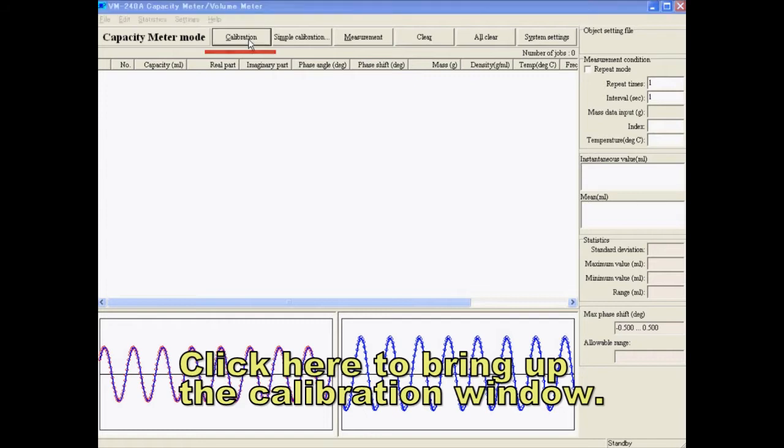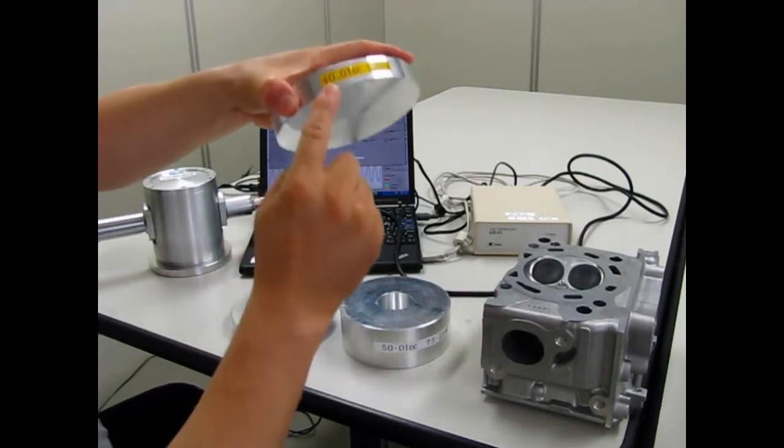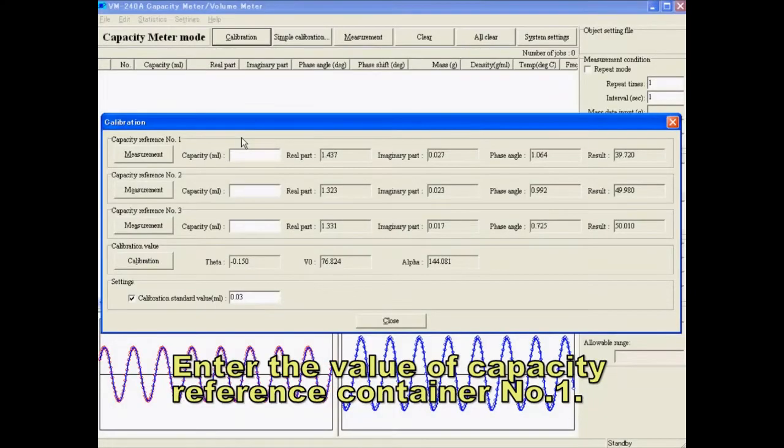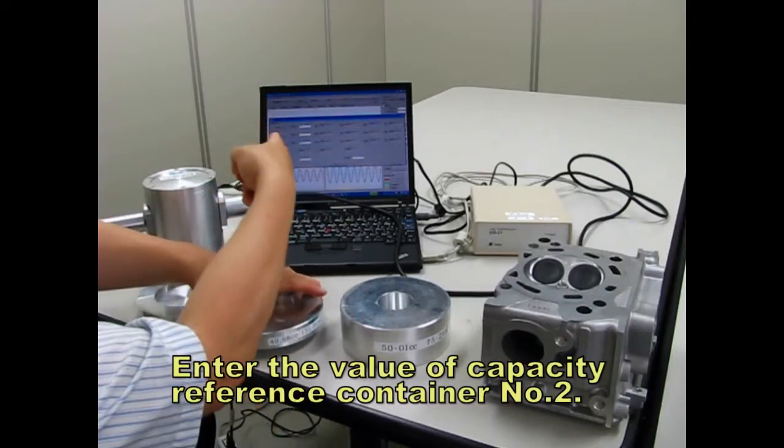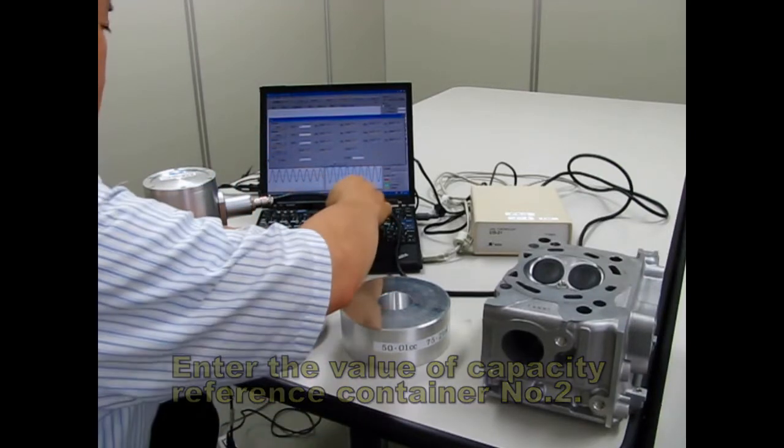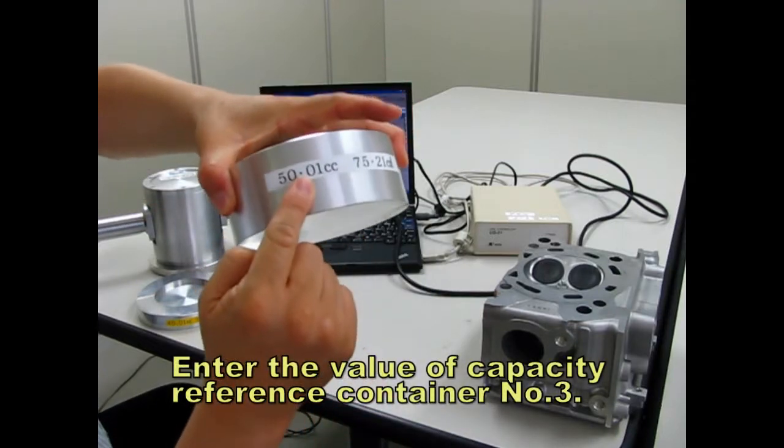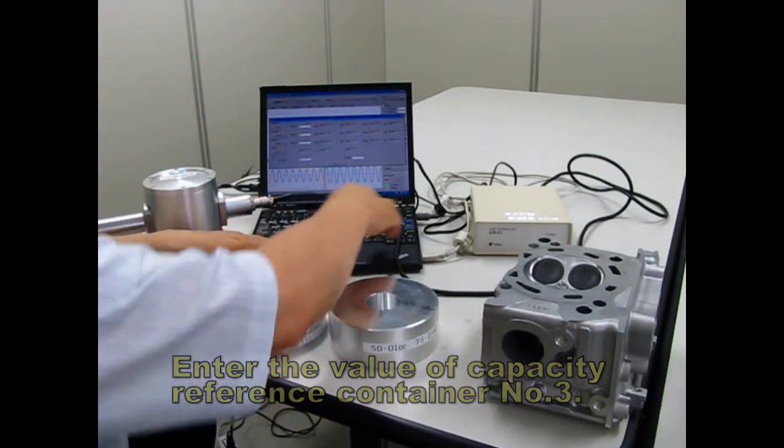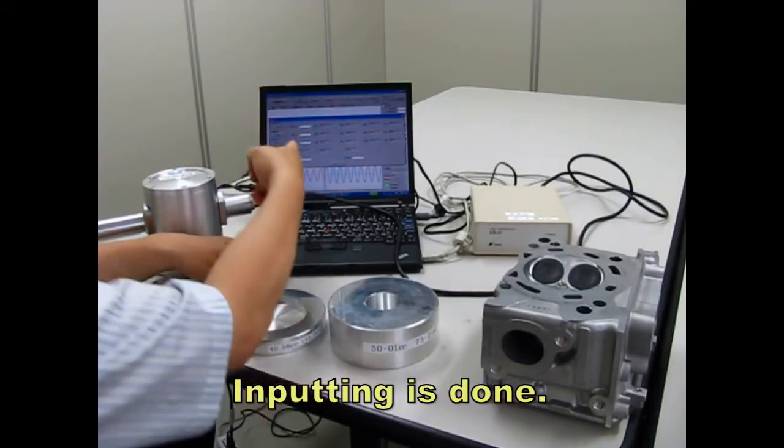Click here to bring up the calibration window. Enter the value of capacity reference container number one. Enter the value of capacity reference container number two. Enter the value of capacity reference container number three. Inputting is done.